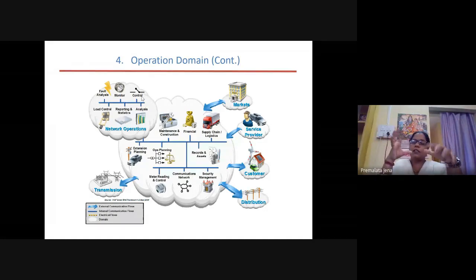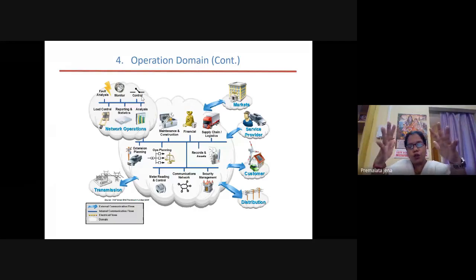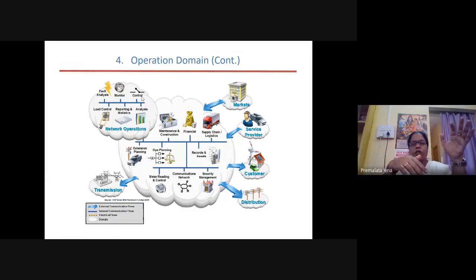The fault analysis part, the programming part, the controlling part—everything comes under this operation domain, and it must ensure that service is resumed. Even though the feeder is out of service due to a fault, the service should again be resumed, and that also comes under the service domain and the operation domain. So this detecting of the fault and detaching the line—opening the circuit breaker or switches—comes under the operation domain.